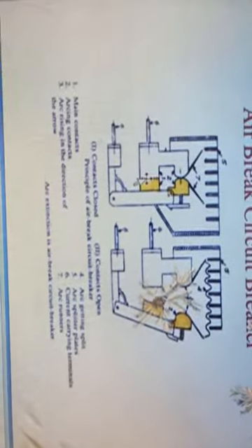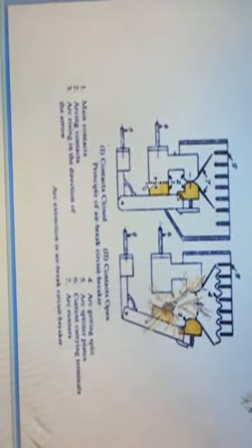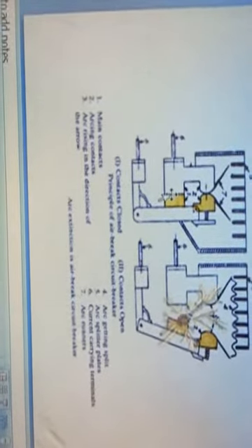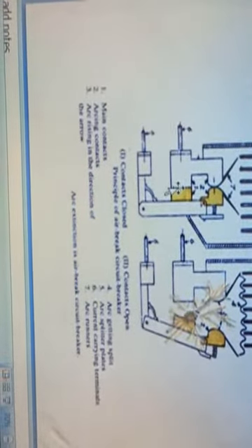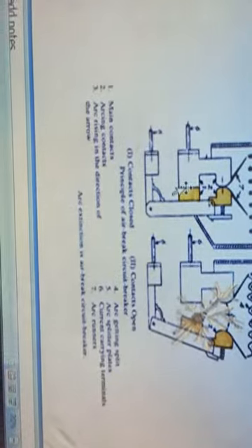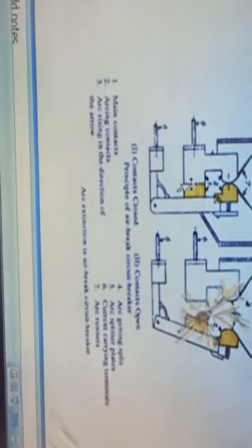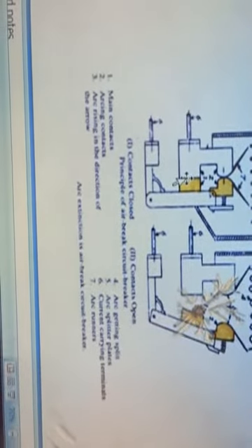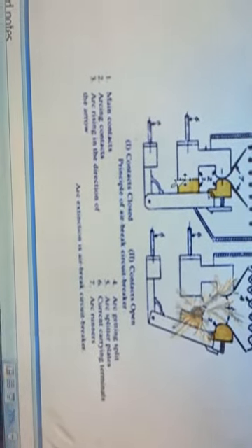So what is the actual use of that? As soon as the arc leaves the vicinity of the contacts, it is transferred to a pair of run-out horns. In doing so, the blowout system is switched on. These blowout coils provide a magnetic field such that the arc footing is subjected to a strong magnetic field.